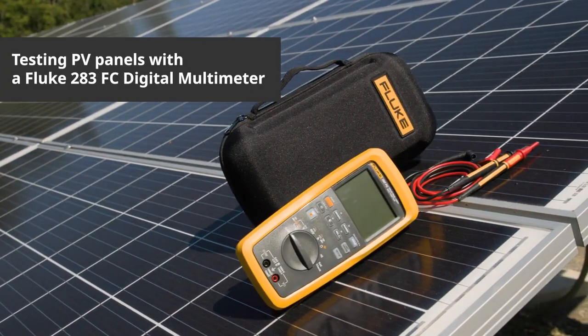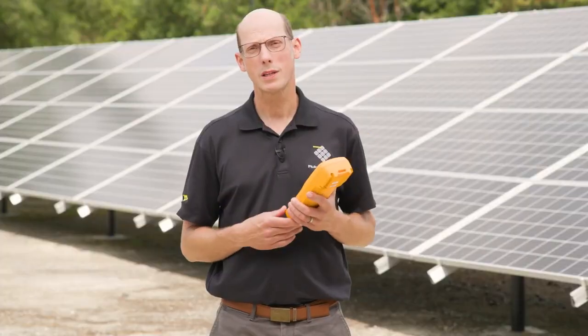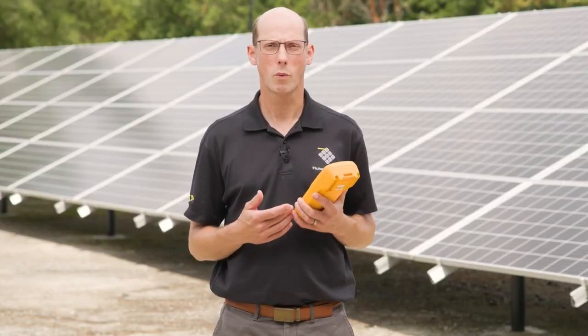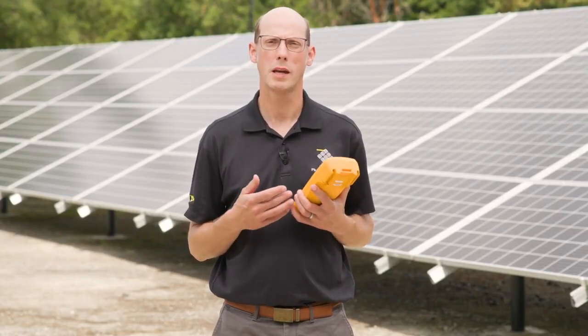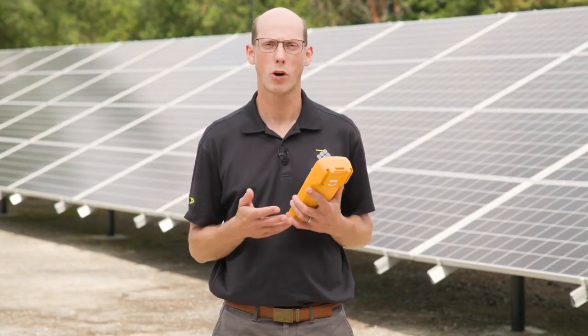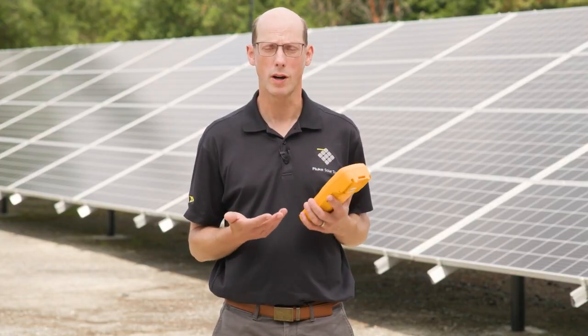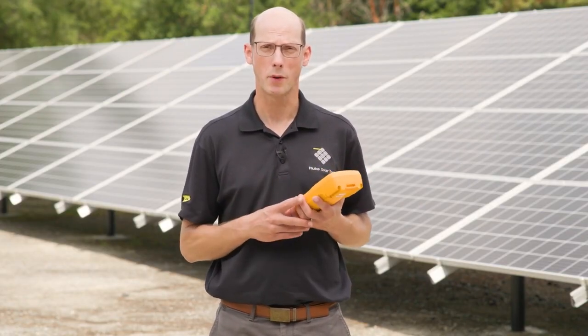We're here to talk about testing solar modules with a digital multimeter. We most frequently test modules at commissioning when we're starting up the system, making sure that the voltage and polarity are correct. We can also do current measurements while the system is operating.